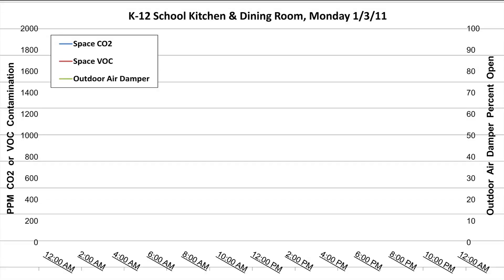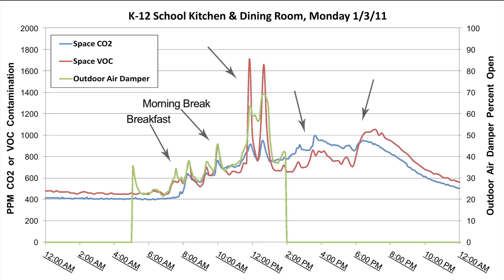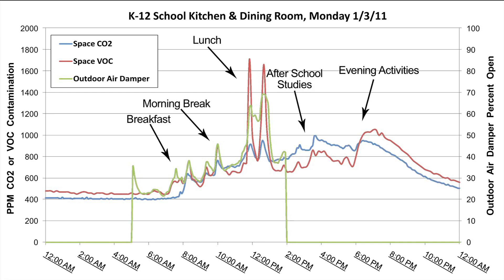These charts show that the output of the VOC sensor has a high correlation to CO2 levels and is reliable, predictable, and repeatable. On Monday, the area goes into occupied mode at 5 a.m., and the outdoor air damper, the green line, begins to track the output of the VOC sensor, the red line.